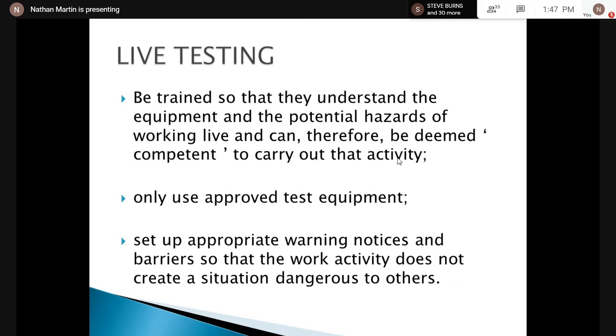One thing I need to point out, and I've done this, but it's not good practice. For instance, you are connecting a new circuit to a panel. Most of the time persons are using the electricity, so you're unable to de-energize. If you're running a new conduit system to a panel, you need a fish tape. If you're unable to get a fiberglass fish tape - remember, fiberglass is non-conductive - it means you're going to have a metal fish tape. If you have a metal fish tape and you're pulling wire into the circuit, you need to be careful.